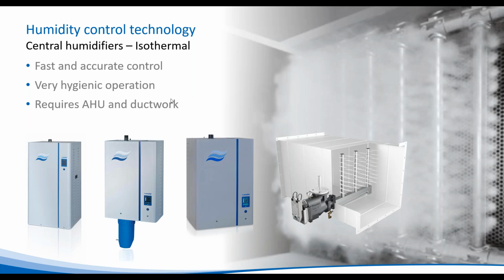Now, you may think that as we're putting steam into the air this will increase the temperature, but actually it only has a very minimal effect. You'll see an increase in temperature from an isothermal humidifier of about 0.5 to 0.75 of a degree. So very minimal, but we will see increased relative humidity as we increase the absolute moisture content in the air.